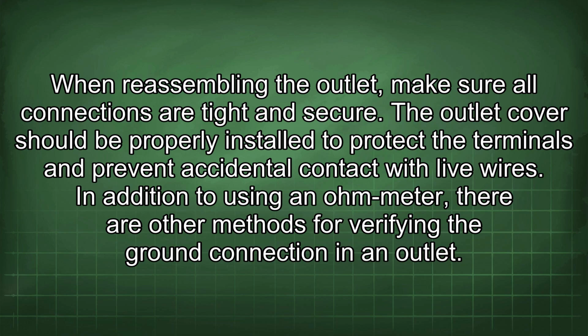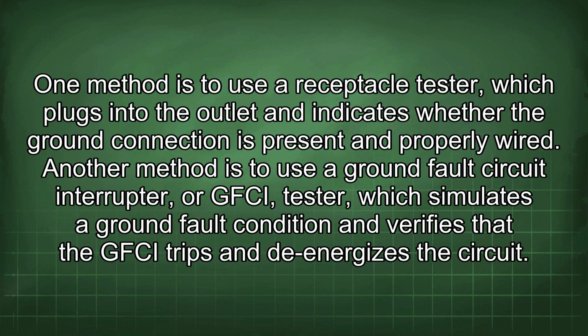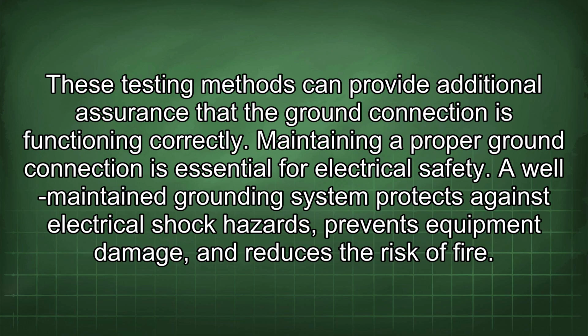In addition to using an Ohm-Meter, there are other methods for verifying the ground connection in an outlet. One method is to use a receptacle tester, which plugs into the outlet and indicates whether the ground connection is present and properly wired. Another method is to use a ground fault circuit interrupter, or GFCI tester, which simulates a ground fault condition and verifies that the GFCI trips and de-energizes the circuit. These testing methods can provide additional assurance that the ground connection is functioning correctly.